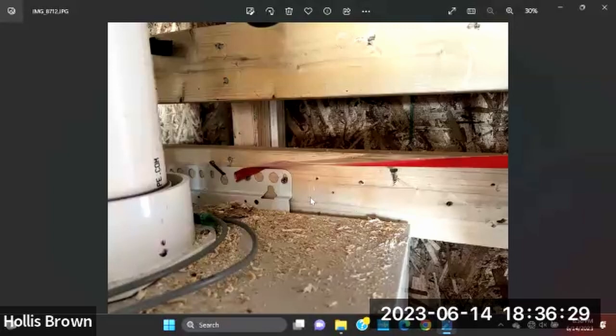So they have no excuse. The fasteners come in the box, and they're called out in the installation manual: use these screws. I'll let them use deck screws if I can recognize them, but they're really supposed to be those nice, big, fat washer head wood screws. That is a safety hazard, because when those snap, we're going to lose the water line and the gas line.